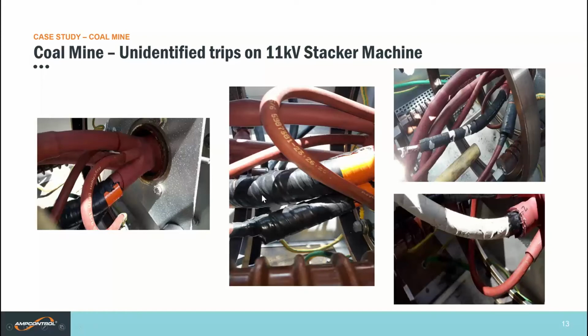The second slide there shows the control core on the bottom and the power core, where they've both been, shall we say, insulated to try and rectify the problem. But as mentioned, all it's done is decrease the air gap between the power core and that control core. Top right hand side, we've taken off the red high voltage tubing from the original termination kit and discovered that underneath, instead of finding the bare rubber core, we've found the core wrapped up in 23 tape. The bottom one is actually what the rubber core looked like once that 23 tape had been removed. Fairly evident that when the semicon was removed off that core, it's basically torn a heap of insulation off that power core. All these little indents, the hollows, the peaks are all points of high stress.